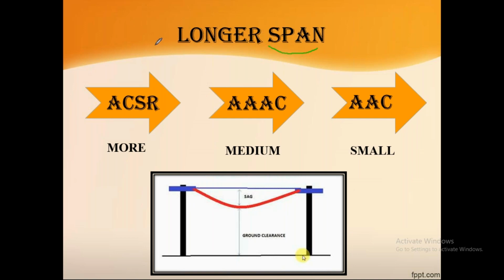Compared among these three, ACSR has more voltage carrying capability than the other two. That's why for long transmission lines, most probably overhead transmission lines, we use ACSR, so the longer span is more for ACSR. Compared to ACSR, AAAC has less, so it is used in medium transmission lines. And AAC is used in the short transmission lines, in the distribution system, because it has less voltage carrying capability. So if the capacity is 230 volts or 400 volts, this type of voltage requires less spanning. So these are the differences among the three conductors in longer span.